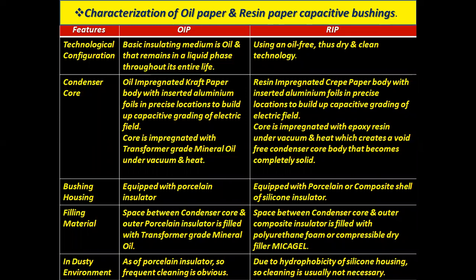Characterization of oil paper and resin paper capacitive bushing. Features. Technological configuration. For OIP, the basic insulating medium is oil, and that remains in a liquid phase throughout its entire life. RIP bushing uses an oil-free, thus dry and clean technology. Condenser core: oil impregnated kraft paper body with inserted aluminum foils in precise locations to build up capacitive grading of the electric field. The core is impregnated with transformer grade mineral oil under vacuum and heat.